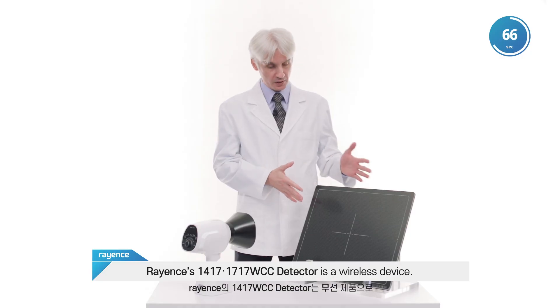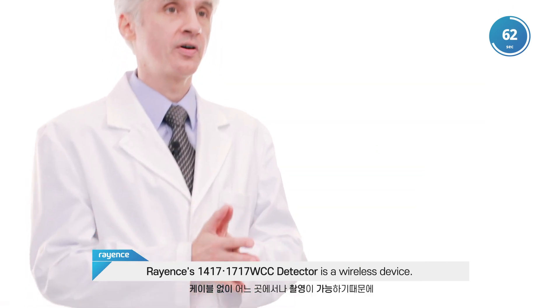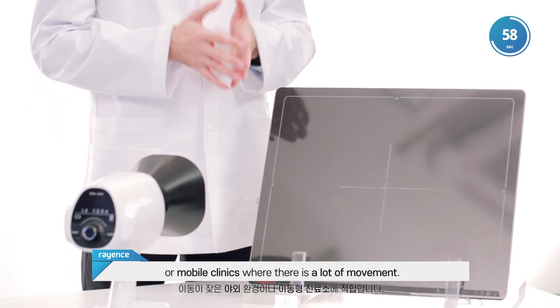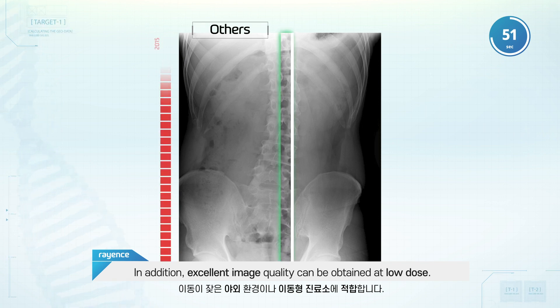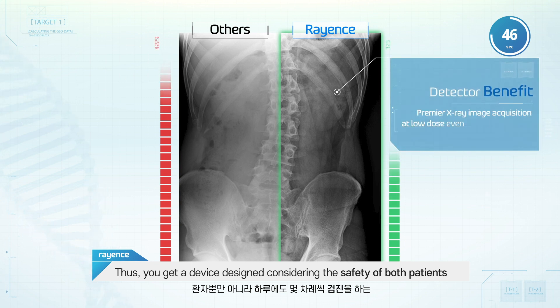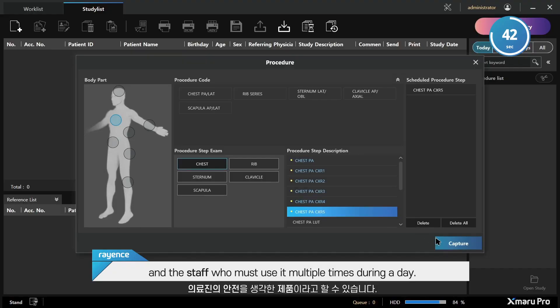Rayence's 1417/1717WCC Detector is a wireless device, so it's suitable for use in outdoor environments or mobile clinics where there is a lot of movement. In addition, excellent image quality can be obtained at low dose. Thus, you get a device designed considering the safety of both the patient and the staff, who must use it multiple times during the day.